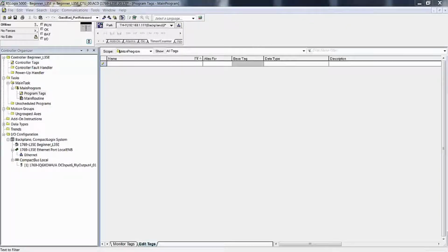Counter instructions: counting events, not units of time. Whereas timer data types accumulate units of time in 1,000th of a second increments, which in itself is a fixed event, counter data types accumulate the occurrences of events unrelated to time. Namely, they accumulate the occurrence of each false to true transition of the rung condition out from the collective state of the conditions preceding the counter instruction in the rung.